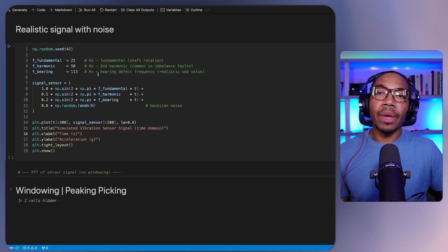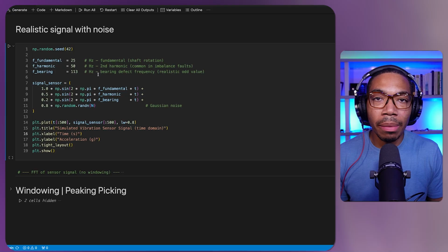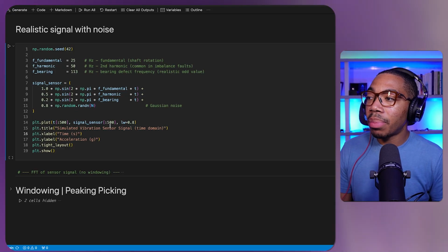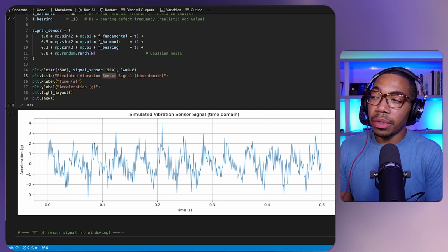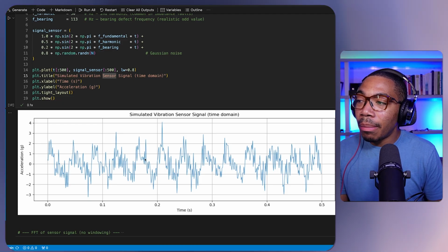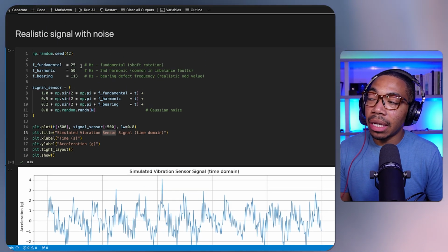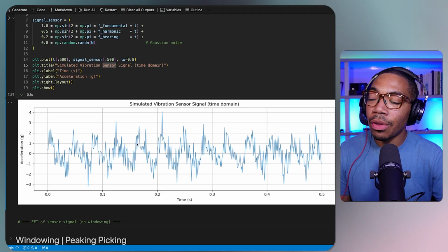So imagine we have something spinning and we have some oddities in the manufacturing equipment. We're going to, again, continue with our simulation data and plot it so you can see what this data now looks like. Now, there should be 3 frequencies here. You could probably see maybe one of them there, maybe another one associated with some of these other peaks. But these frequencies don't exactly line up. We have the harmonics, and then we have this odd value there. And it's really hard as a human to see this. We maybe recognize a pattern, maybe don't.